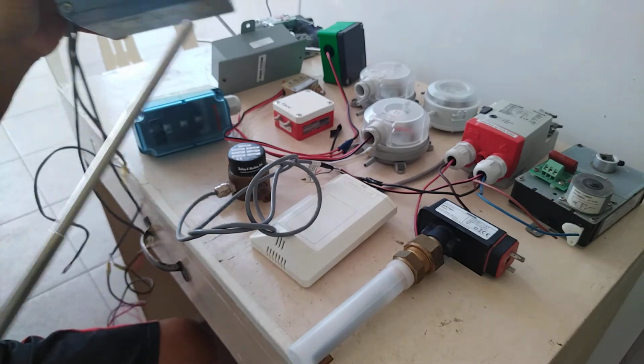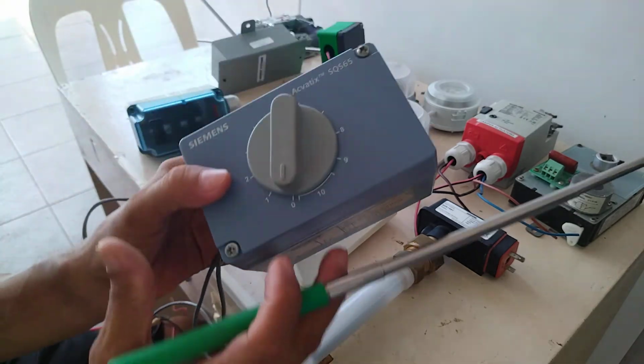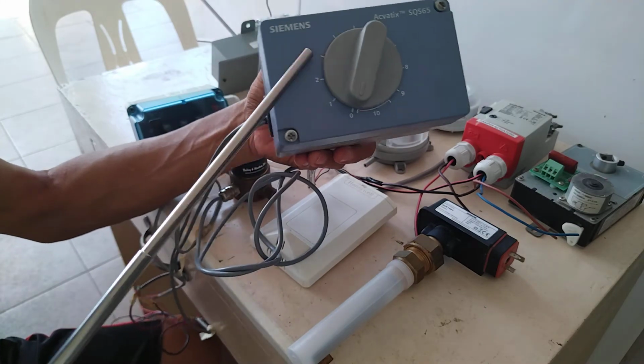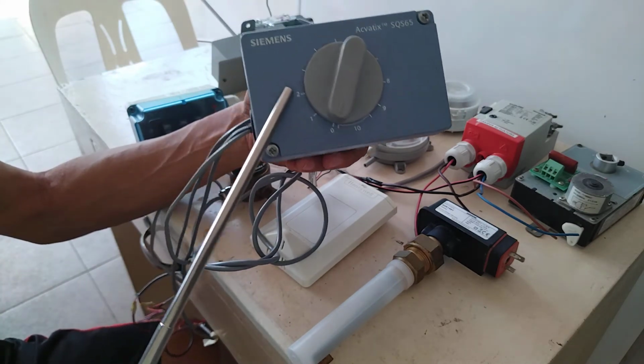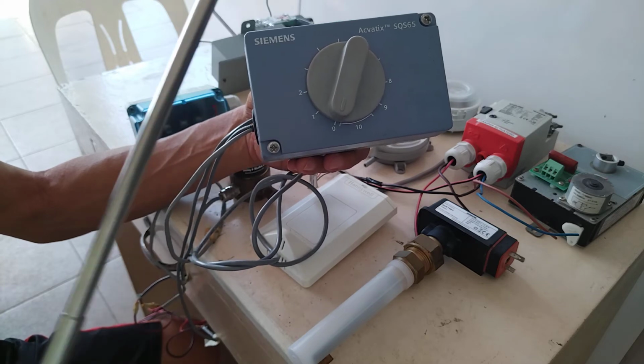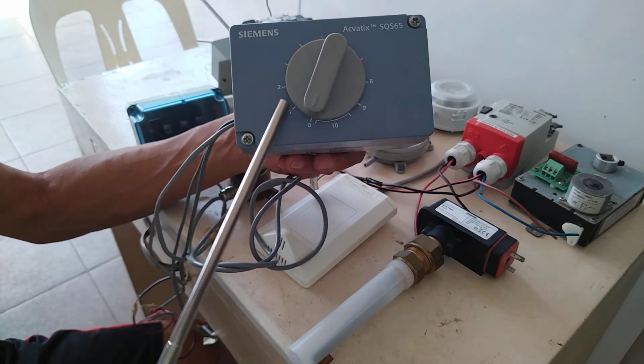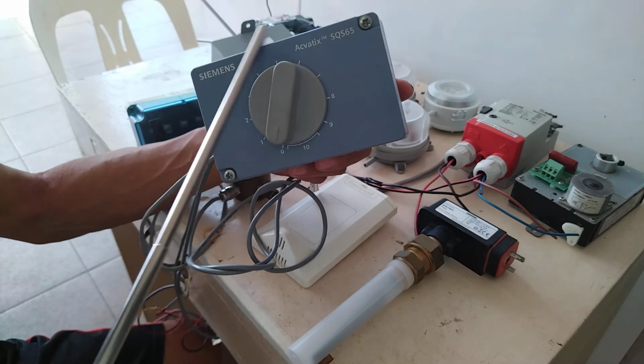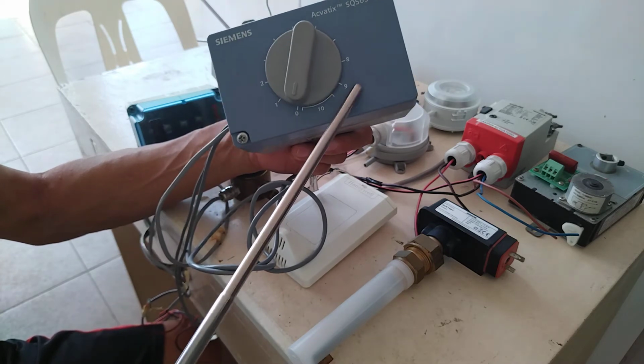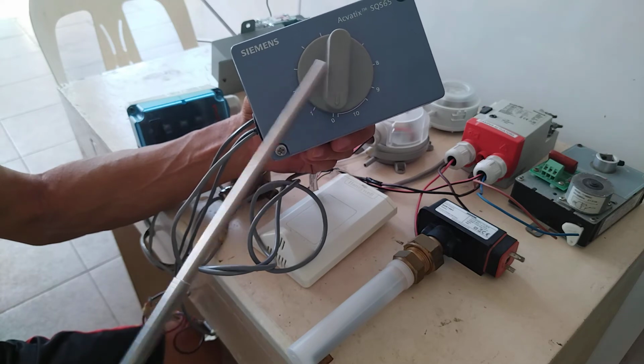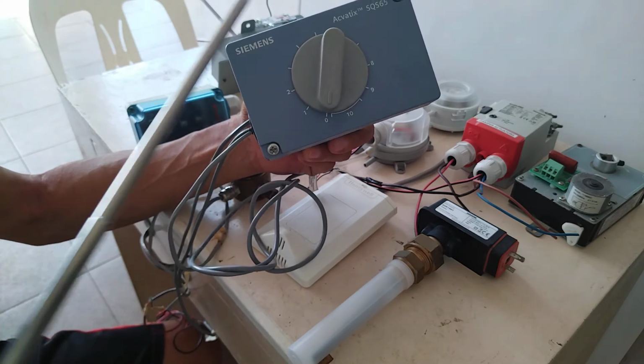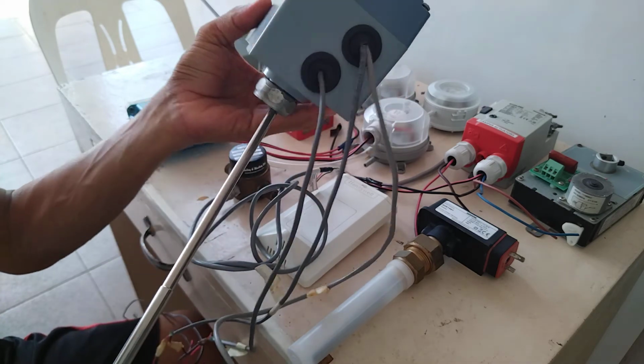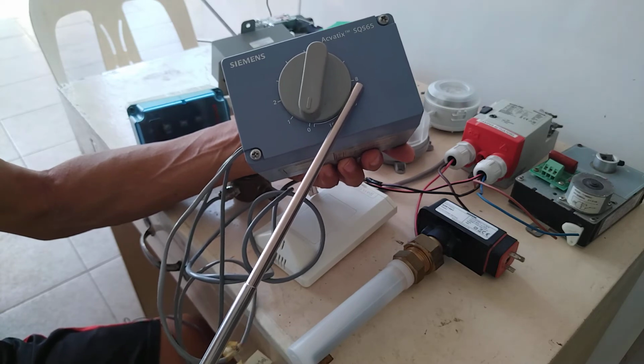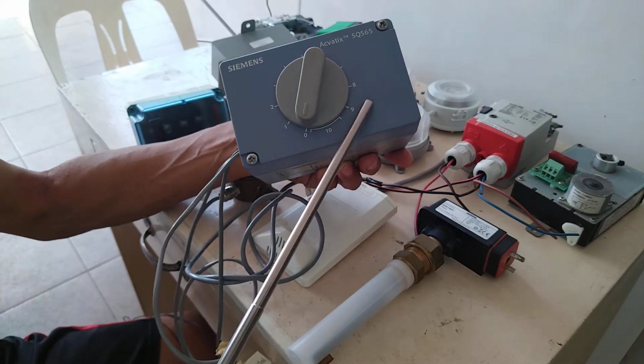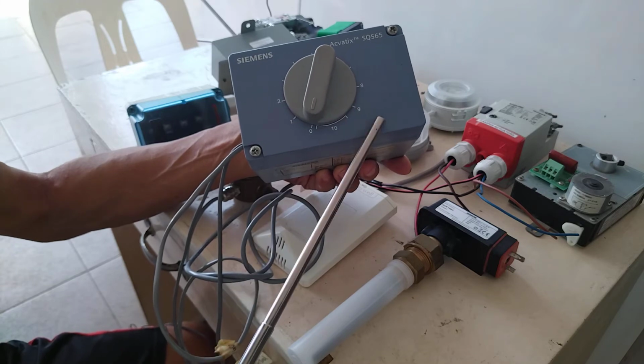Now, again, we have here one device. This is one of the important devices you will encounter in the field. Now, this one is a valve actuator. The purpose of this valve actuator is to open and close. Actually, this is modulating, as you can see here, from 0 to 10 or 0 to 100% opening. So this valve will move, or open and close, okay? We are attaching this to the valve stem. So this one will be the one to open and close the valve based on our control logic program, which is a PID controller, okay?